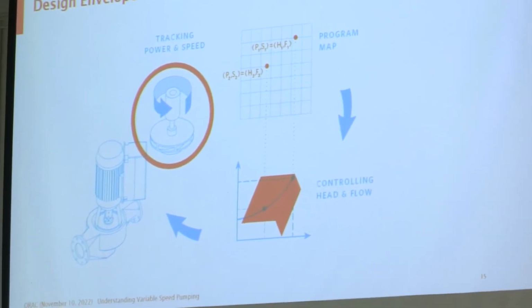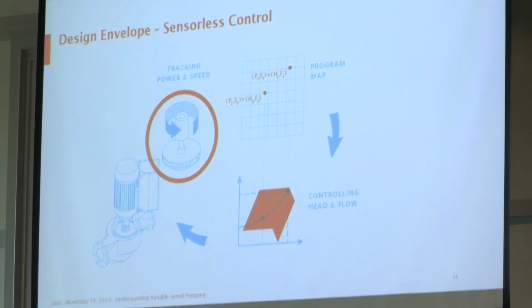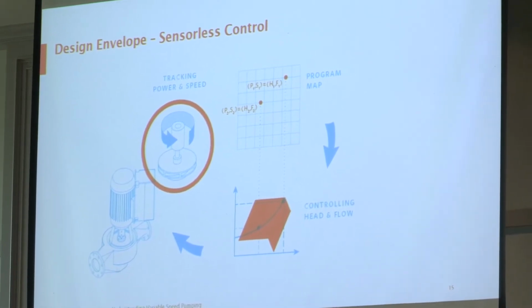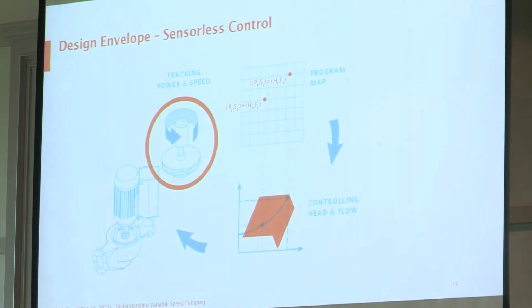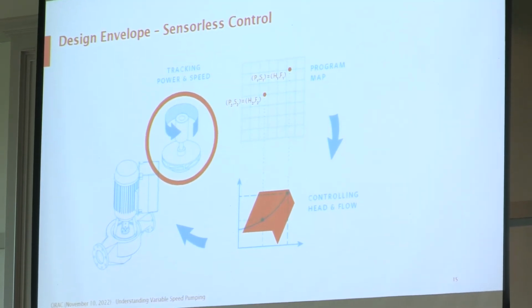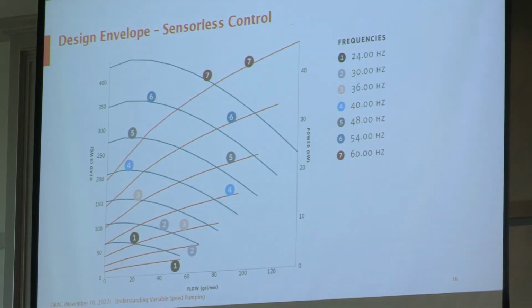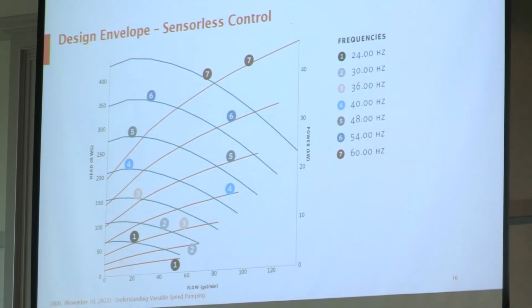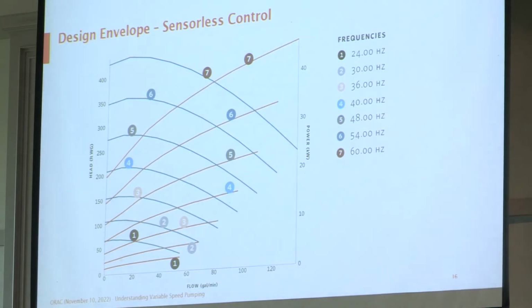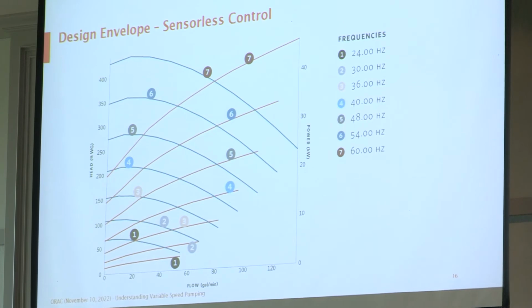First of all, what we're doing is we're monitoring the speed and the power the pump is operating at, and then adjusting accordingly when that changes as valves open or close and loads change in the system. What we do, and what everybody does, is this is a mapped performance. We take that pump, put it on a test rig, and run it through a series of speeds. And at those different speeds, we plot the power to head at that speed and the power to flow at that speed.